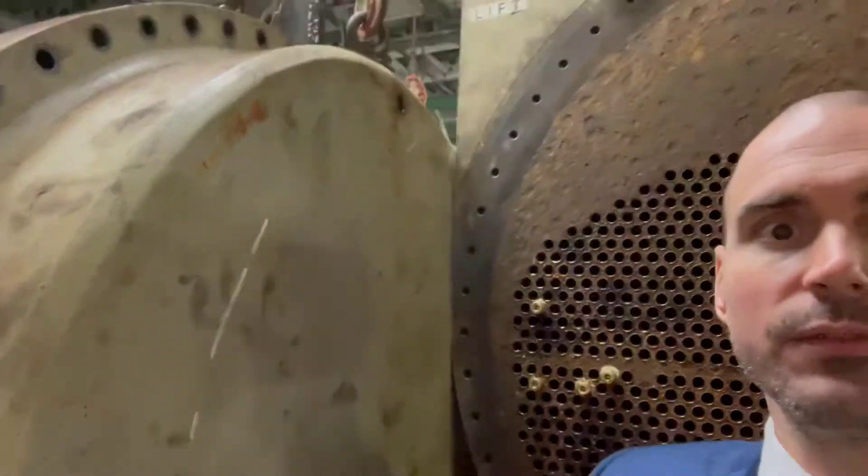I think that's really cool — it's something that isn't talked about enough. We've got all of the apparatus and everything to lift all of the equipment, get in there, and clean the tubes out. We actually did eddy current tests earlier this week on our chillers.